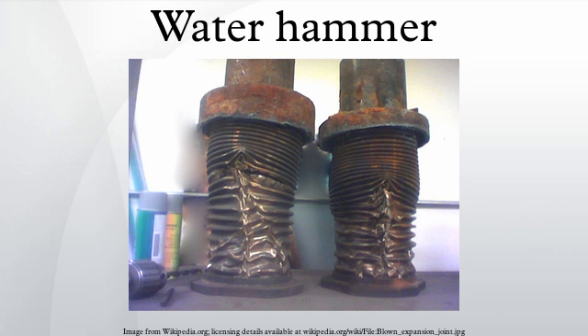The following characteristics may reduce or eliminate water hammer: reduce the pressure of the water supply to the building by fitting a regulator. Lower fluid velocities. To keep water hammer low, pipe sizing charts for some applications recommend flow velocity at or below 1.5 m/s. Fit slowly closing valves. Toilet fill valves are available in a quiet fill type that closes quietly. High pipeline pressure rating. Good pipeline control.